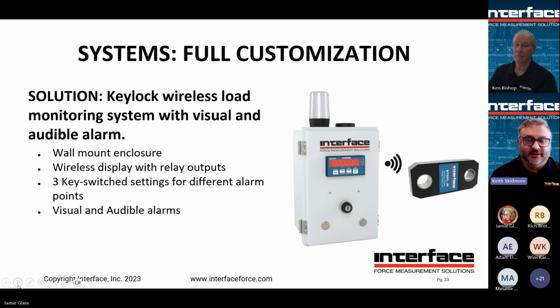And so when they're lifting this device or object, if it starts to hang up or whatever, they'll know it. Again, the operator may not be paying attention. This will get his attention, the light, and then of course the audible alarm will notify. And then again, when they change articles in production, the manager comes over and switches the switch, and then walks away with the key so that it's always set up properly for that operation.